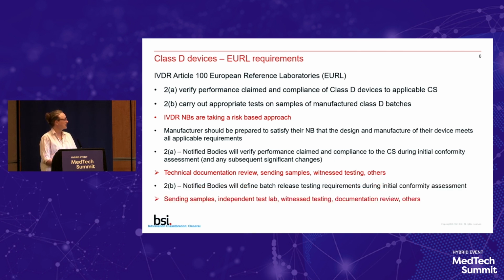So then the notified bodies are defining the batch release testing requirements during initial conformity assessment. And again, this can include sending samples, using an independent test lab. There currently isn't one, but we're working together to try to source independent testing laboratories. Again, witness testing, deeper dives of documentation review, and others. Anything that we might think of during conformity assessment that reduces that risk to patients.